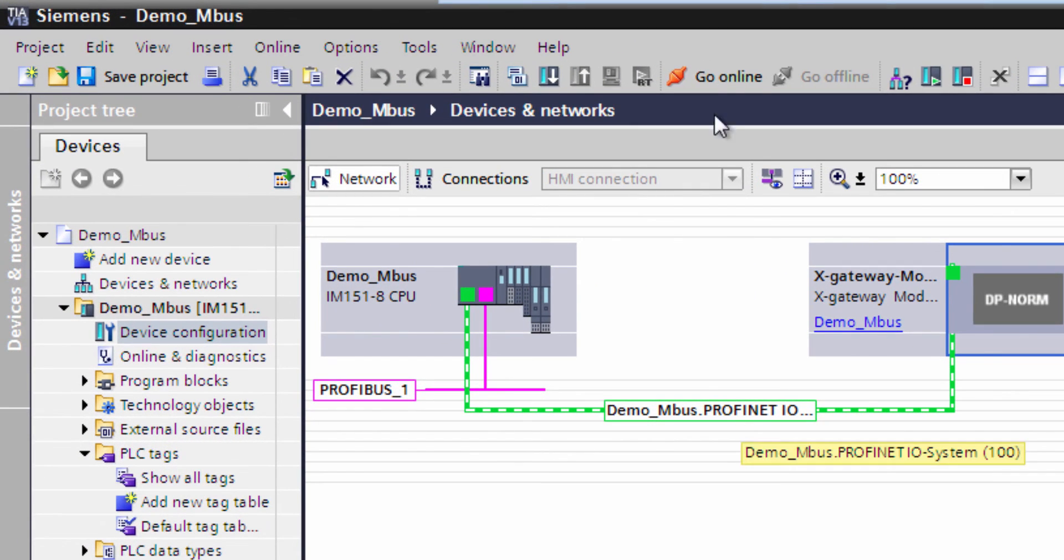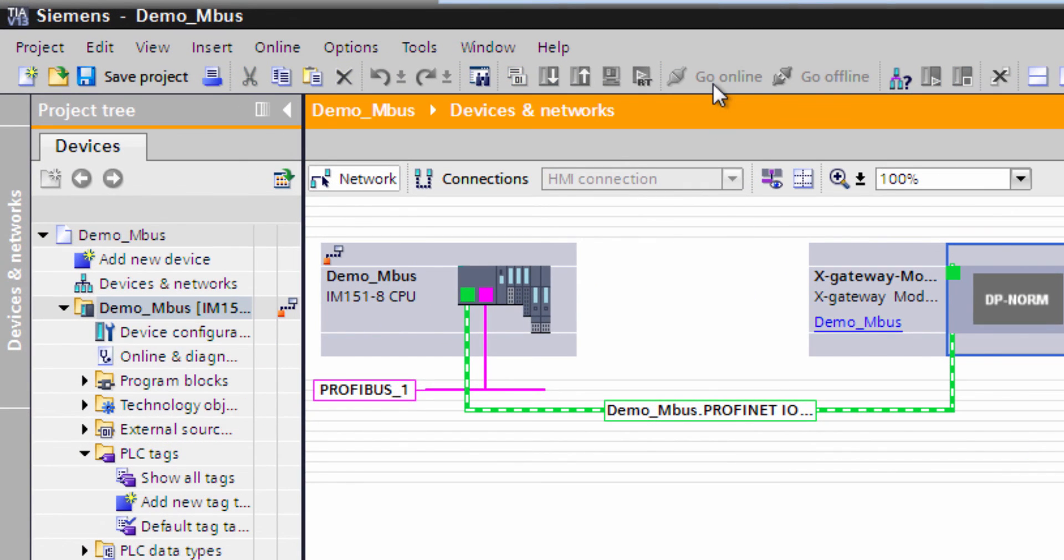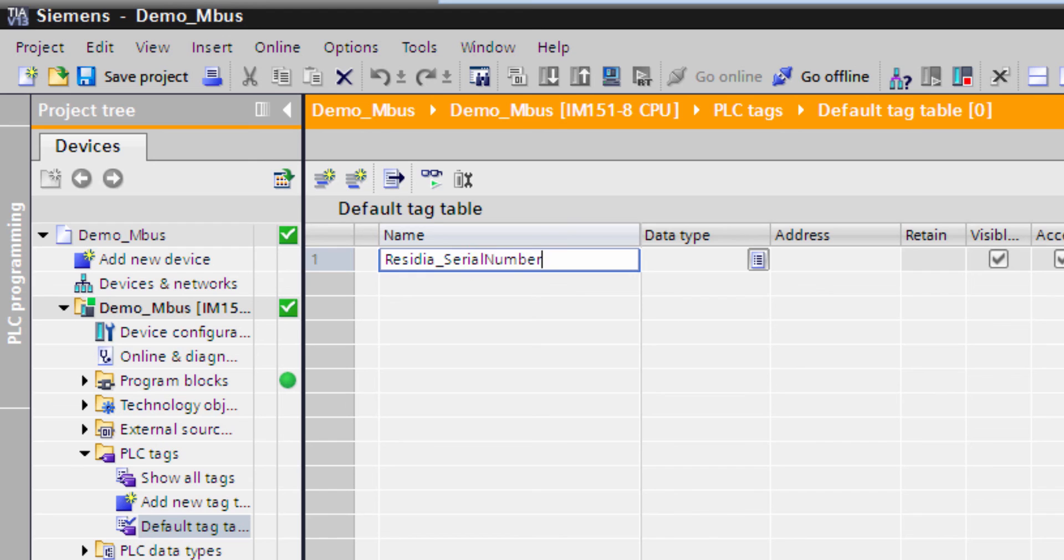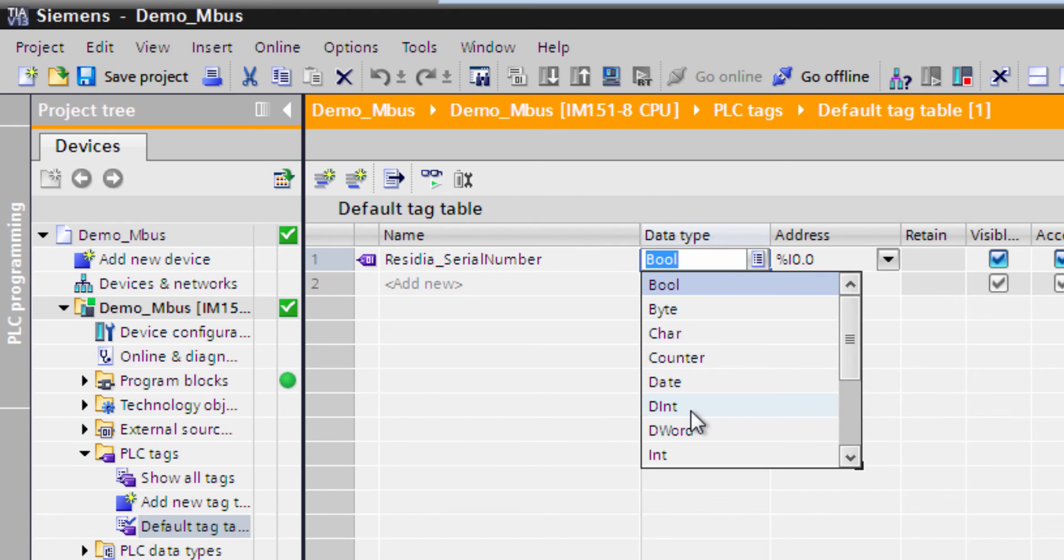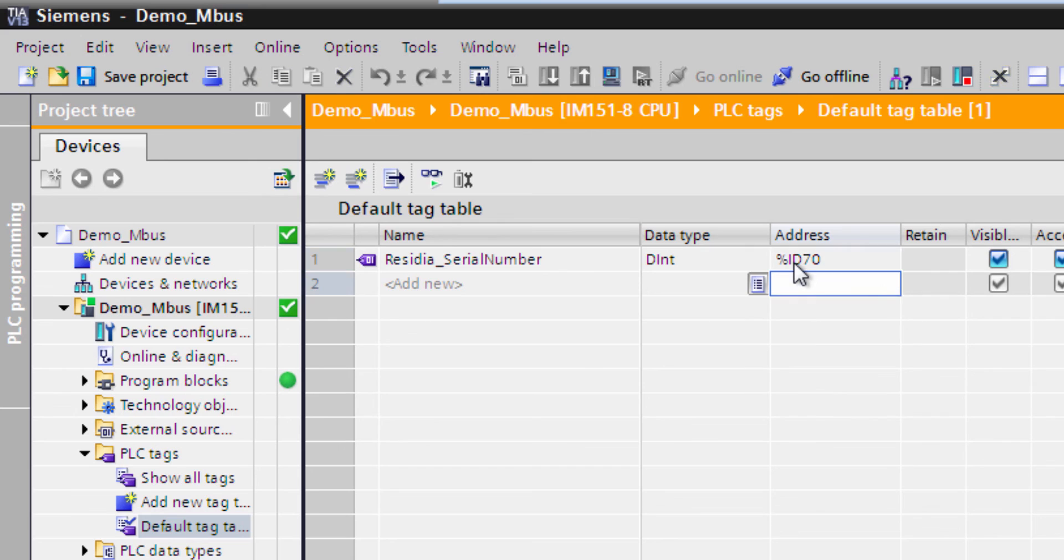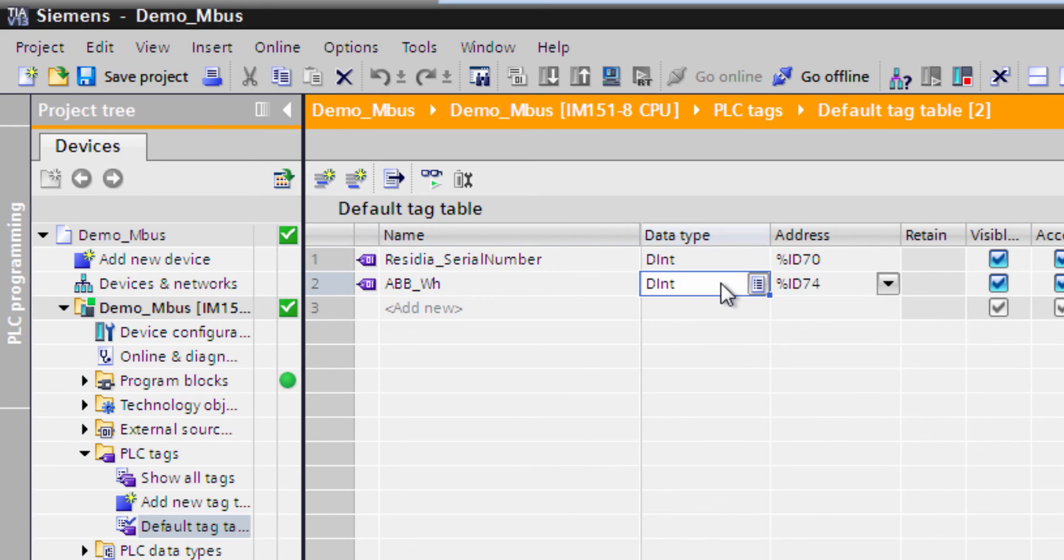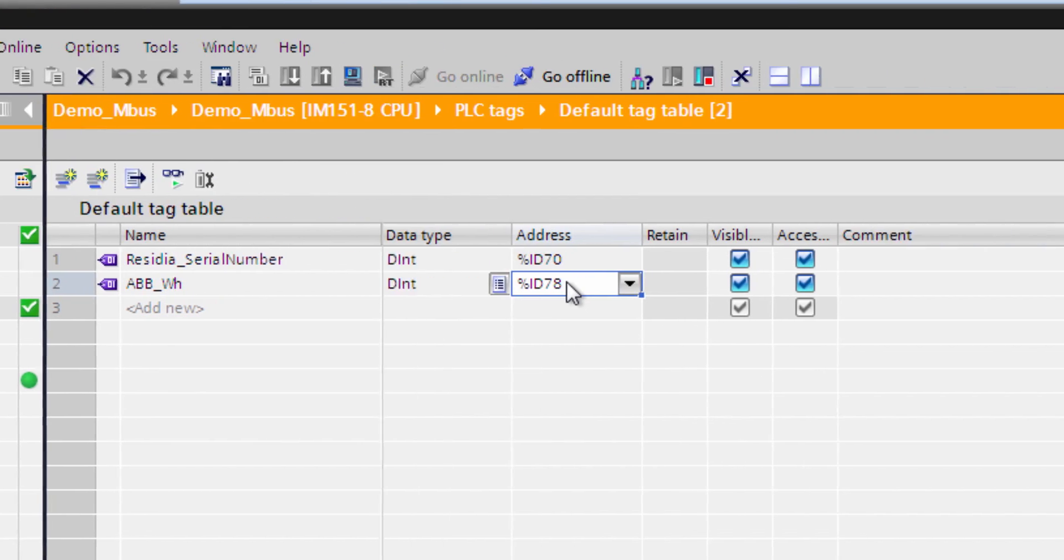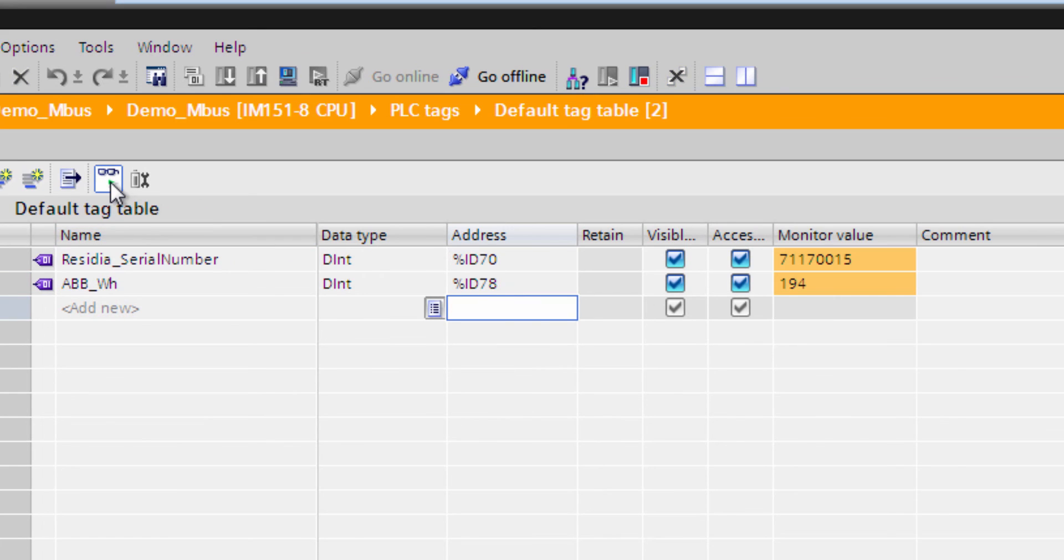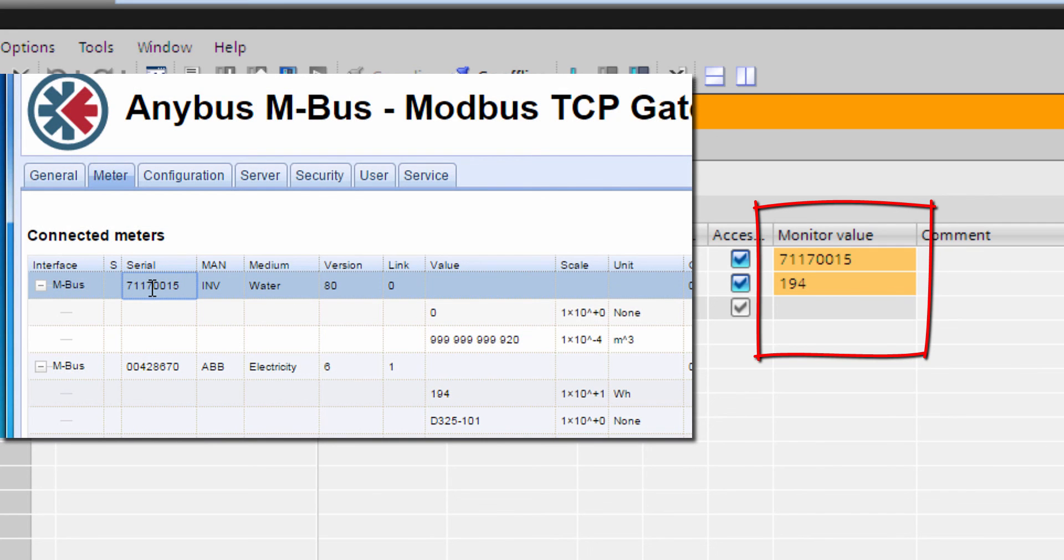I can now go online and into our tag list and add our two values. First, Residia Serial Number. This is a double integer located at ID 70. Then we have ABB Watt hours, which is also a double integer at ID 78. I can see that the values from the MBUS devices now show up. If I compare them to the values in the Anybus-MBUS gateway, I can see that they are the same.